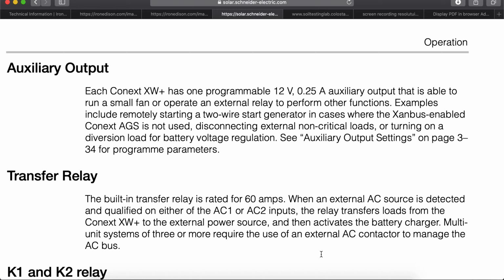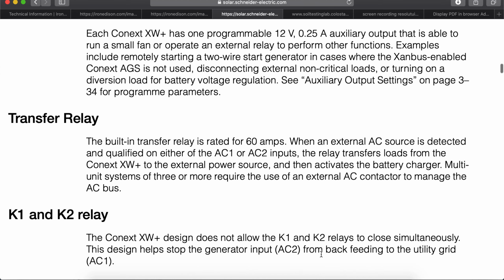Auxiliary output. Each Conext XW Plus has one programmable 12-volt, 0.25 amp DC auxiliary output that is able to run a small fan or operate an external relay to perform other functions. Examples include remotely starting a 2-wire start generator in cases where the Xanbus enabled AGS is not used, disconnecting external non-critical loads, or turning on a diversion load for battery voltage regulation. See aux output settings on page 3-34 for programming parameters.